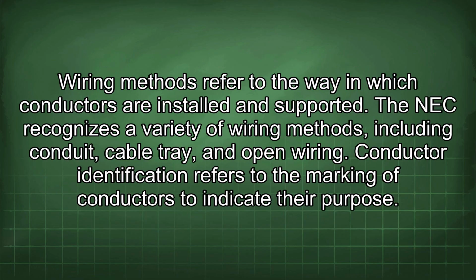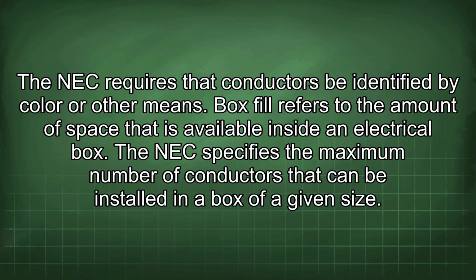Wiring methods refer to the way in which conductors are installed and supported. The NEC recognizes a variety of wiring methods, including conduit, cable tray, and open wiring. Conductor identification refers to the marking of conductors to indicate their purpose. The NEC requires that conductors be identified by color or other means. Box fill refers to the amount of space that is available inside an electrical box. The NEC specifies the maximum number of conductors that can be installed in a box of a given size.